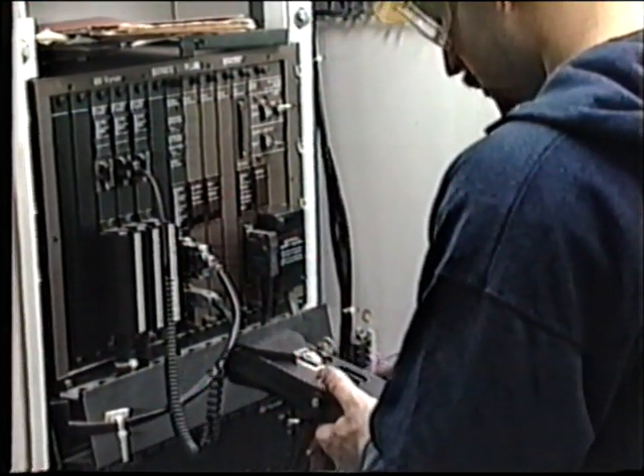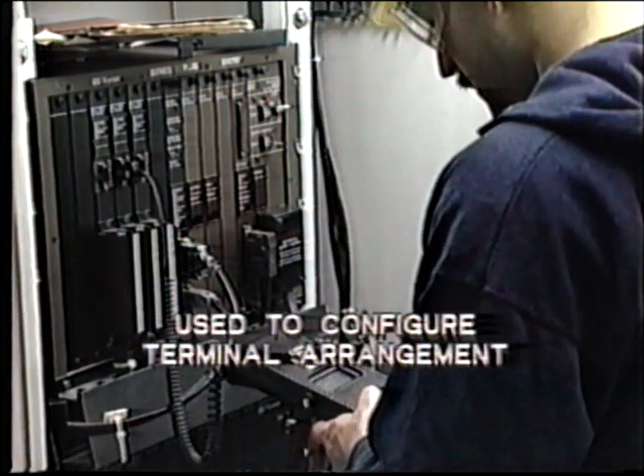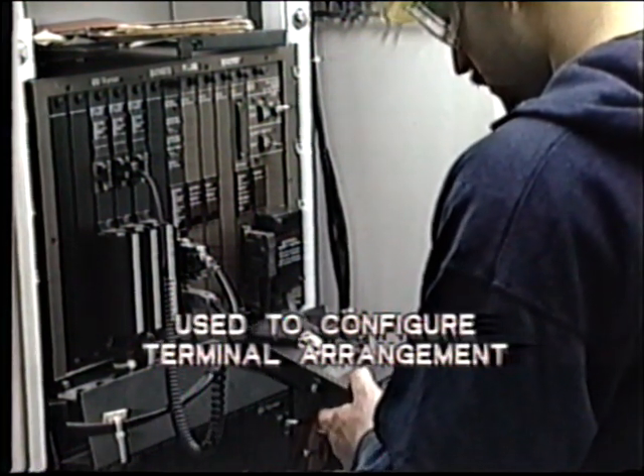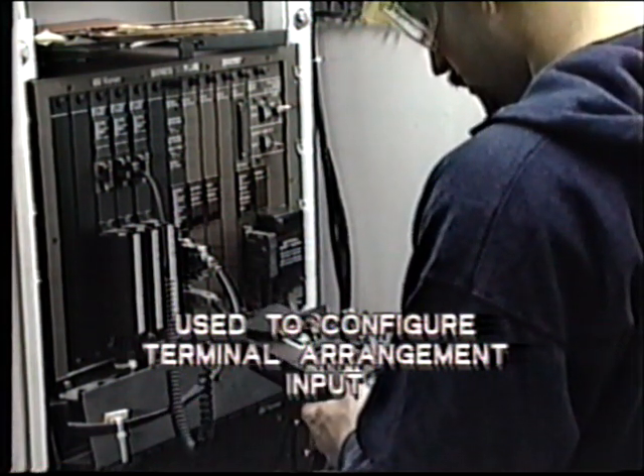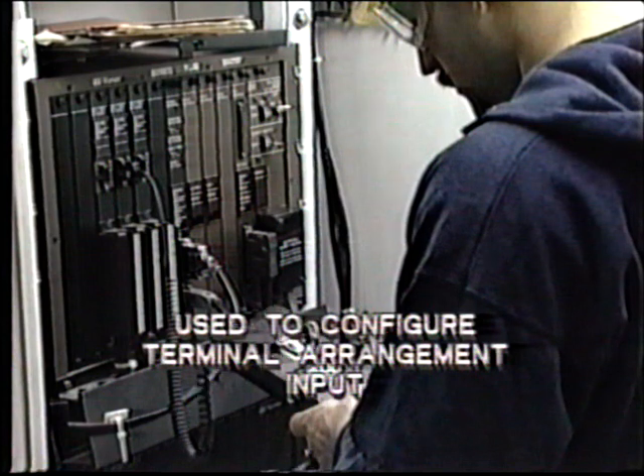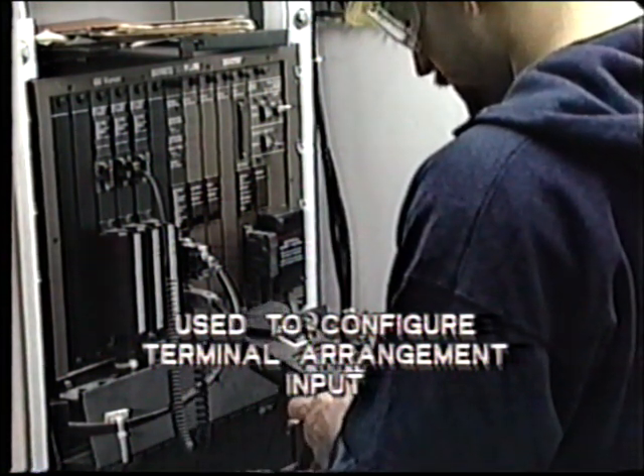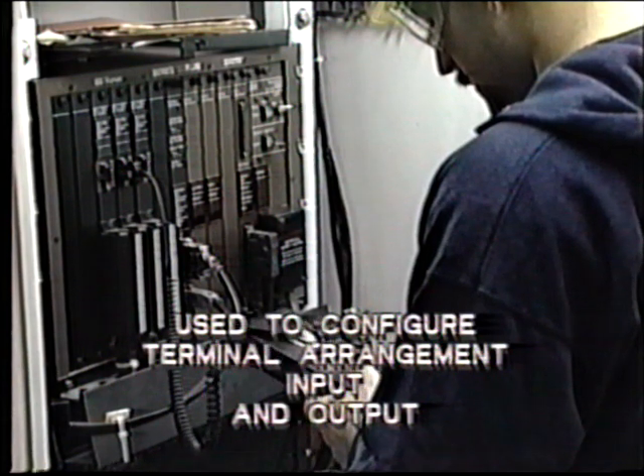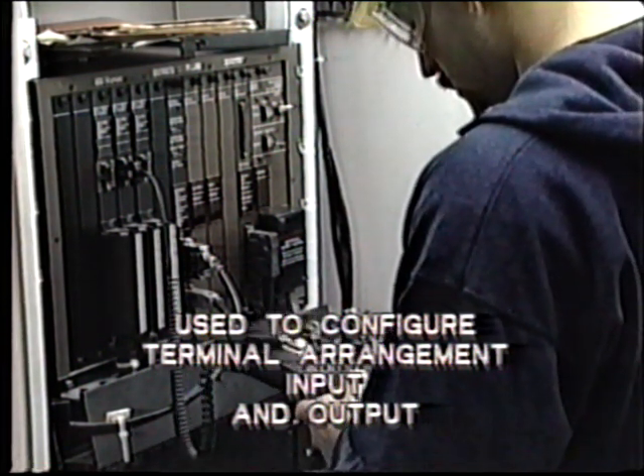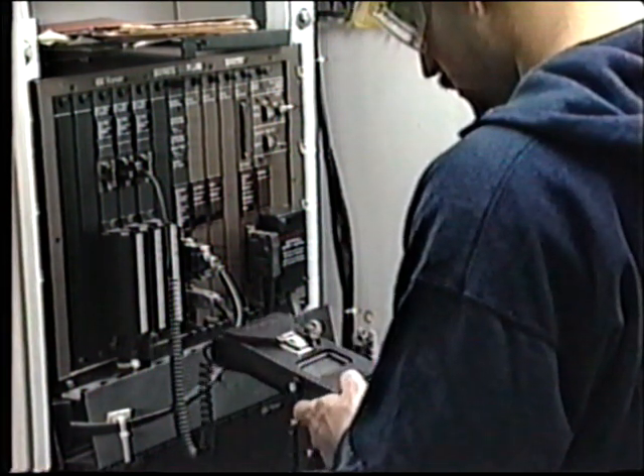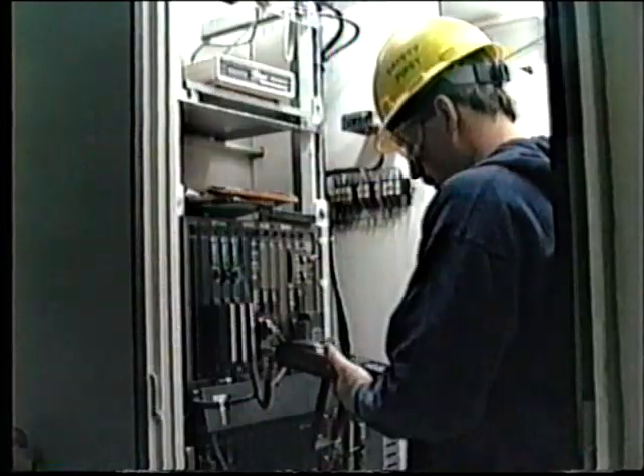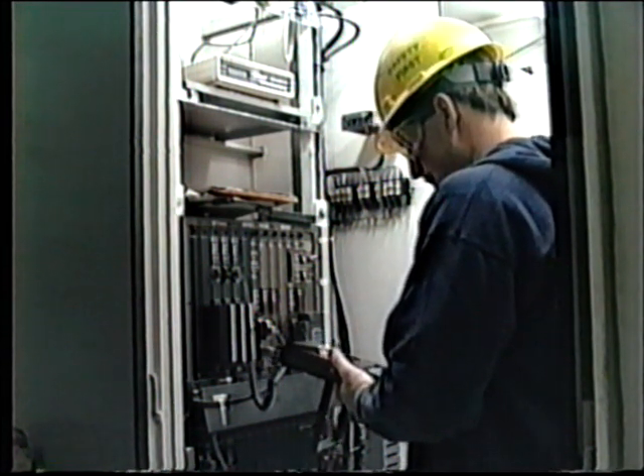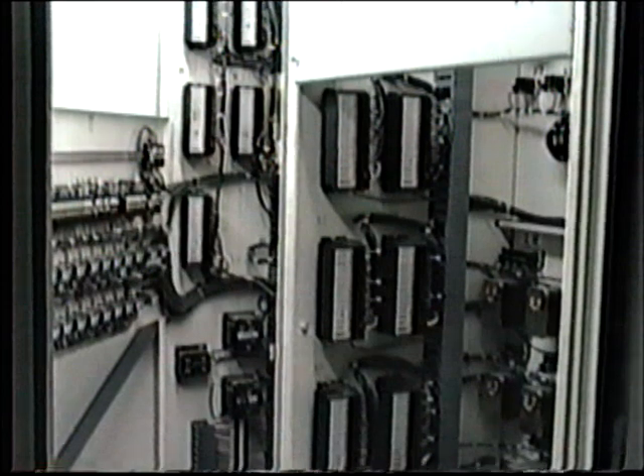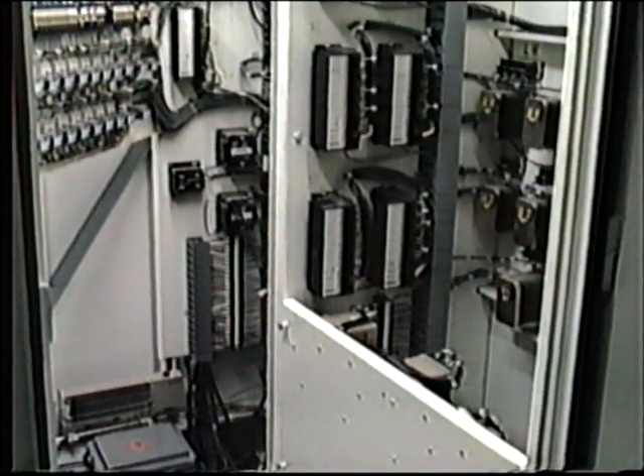When each input-output block is installed, the handheld monitor is used to configure the terminal arrangement. That is, to make each circuit suitable for the type of input, say analog or discrete signals, either AC or DC. Similarly, the output circuits must also be configured to meet the requirements of the output control devices. Alarm levels and other control parameters can be set using the monitor. A very important feature is its diagnostic capability. Each of the control loops can be checked out, including the hardware. This allows us to check control circuits even before they are commissioned and placed in service.